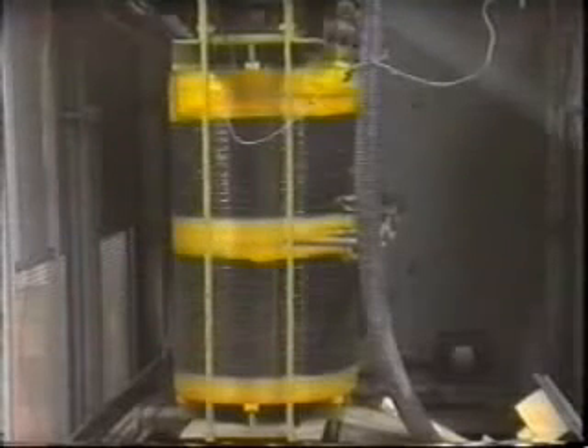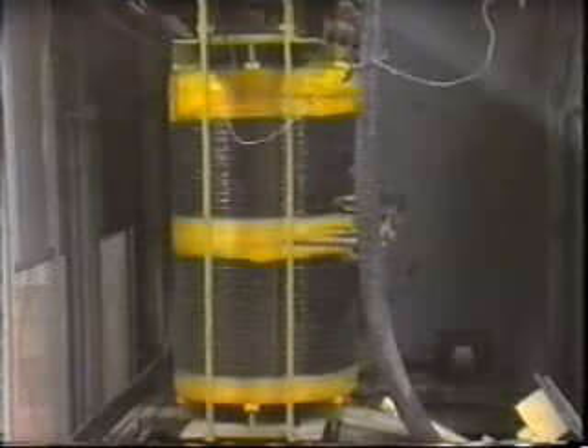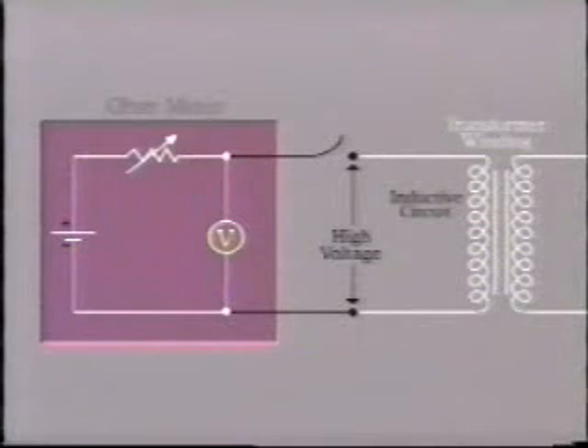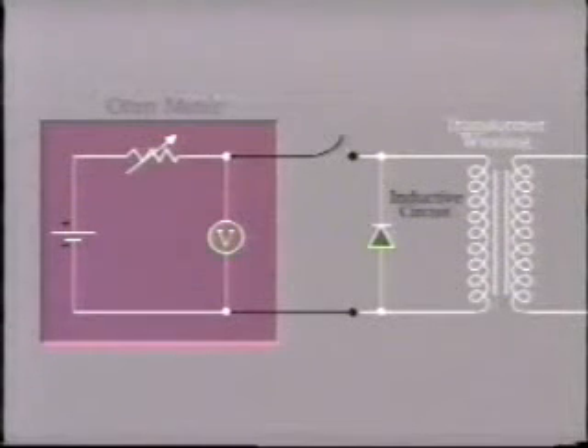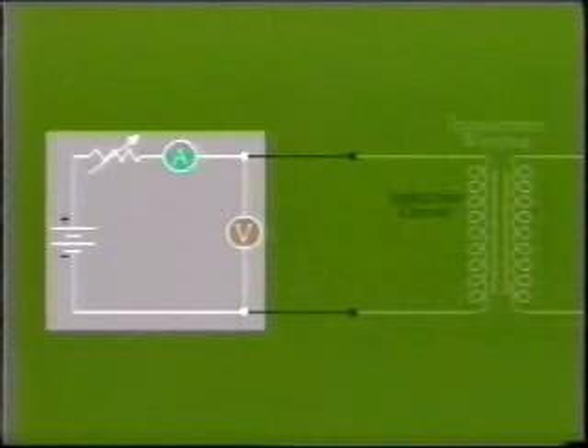You must take special care when measuring the DC resistance of an inductive circuit, for example, a transformer winding. If the test circuit is interrupted by removing the test lead, a high voltage surge will appear across the test terminals, probably exceeding the maximum allowable input voltage. One method of protecting against this problem is to connect a diode across the winding. The preferred method of measuring resistance in an inductive circuit is by measuring volts and amps, remembering to vary the current gradually.